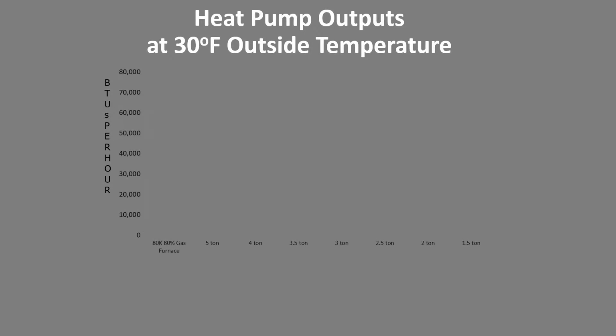Another way of looking at heat pump sizing is just to recognize that if our goal is to have a balance point of 30 degrees, we really don't care about design temperature. We could actually do the heat loss of the house at 30 degrees, no matter where you are, in Port Angeles or Pocatello. It's still 30 degrees outside. So our house is going to have a heat loss of about 30,000 BTUs at 30 degrees. Well, there's our 80K furnace, easily handles it, probably a little too big to tell you the truth. Our 5 ton system easily covers it. Our 4 ton system covers it. 3.5 ton system nails it perfectly.